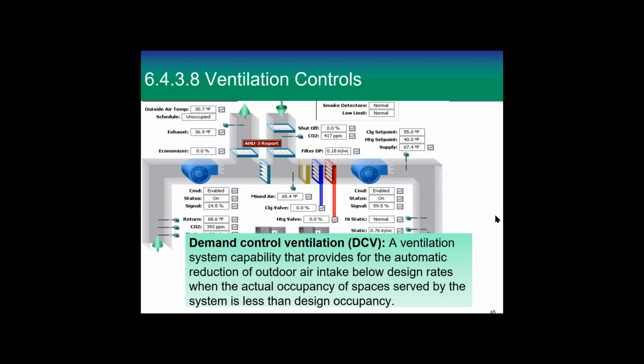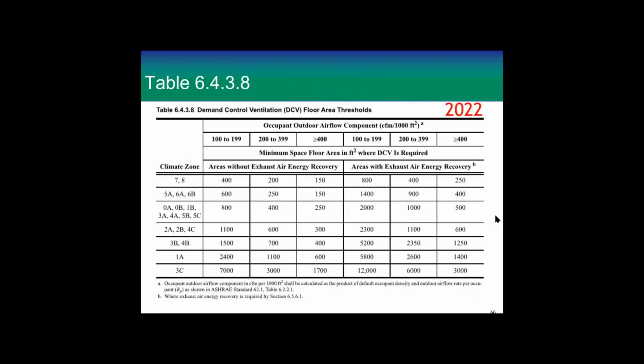Let's see. So here's that table. You may have forgotten I was about ready to show you a table. This is a new table. It's a different way to approach this problem. So here's the climate zones. Here's the areas without exhaust energy recovery. Here's areas with exhaust energy recovery, because this changes how much energy you're using. And then this is occupant outdoor airflow components, CFM per 1,000 square feet.